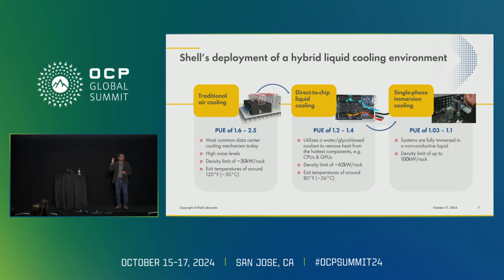Now we are actually close to less than 1.1 on the PUE. The range of 1.03 is probably the goalpost everyone wants to achieve. Because this is an existing data center, I cannot change the cooling infrastructure outside the building, so I have to stick with what we have with respect to chillers and evaporators. So with the given system, just by changing the cooling technologies, I can bring changes. I think this is a living example, and we can showcase it if somebody is interested to come over.